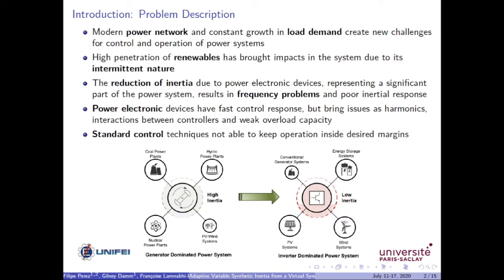So the modernization of the power network and the constant growth of the load demand create new challenges for the operation and control of the power systems. The first big challenge is the high penetration of renewables, which has brought some impacts to the system due to the intermittent nature of this kind of energy. And also the reduction of inertia related to the power electronic devices that represent a significant portion of the generation of a power system now. So it may result in frequency problems and poor inertial response.